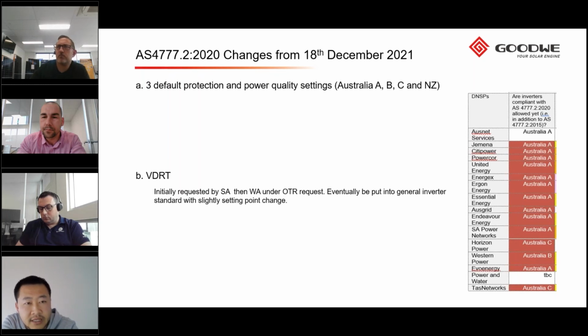The first one is the country setting code. The current standard means each DNSP, each distributor power supplier, has their own grid connection protection setting points. That means either the installer needs to manually set up these points when they commission the inverter, or the inverter supplier gives the whole DNSP list, so the installer just needs to select the relevant DNSP code when commissioning. But after December, under the new standard, the standard only requires the inverter supplier to set up four grid connection settings on the inverter, which are A, B, C, and the New Zealand standard. Then each DNSP will nominate which code they selected. So in future, instead of selecting the DNSP, the installer just needs to select either Australia A, B or C according to where they install the system.